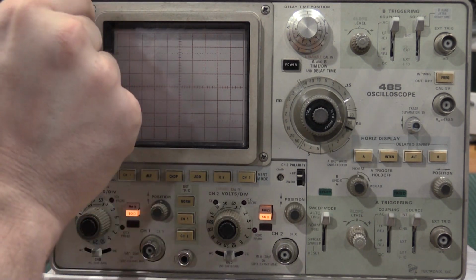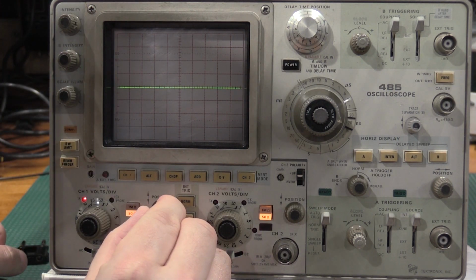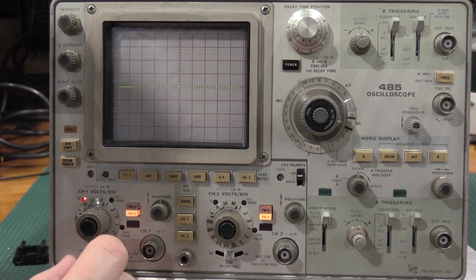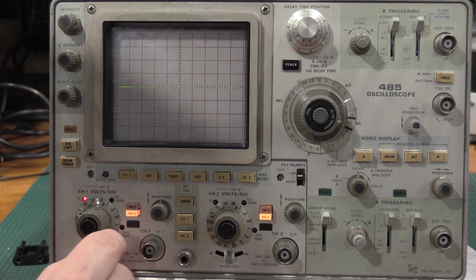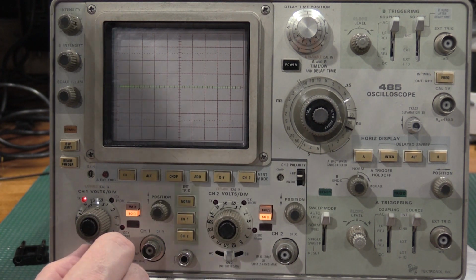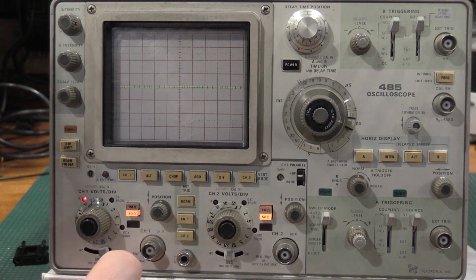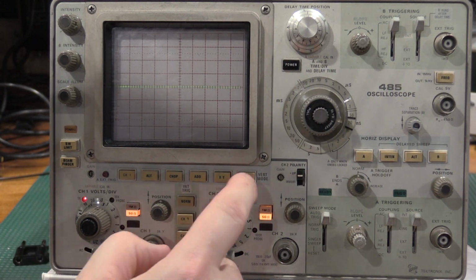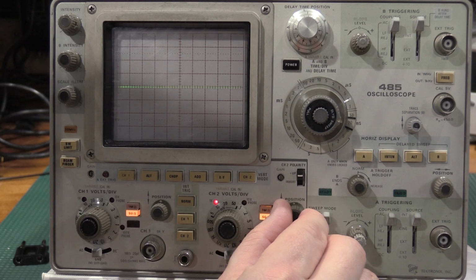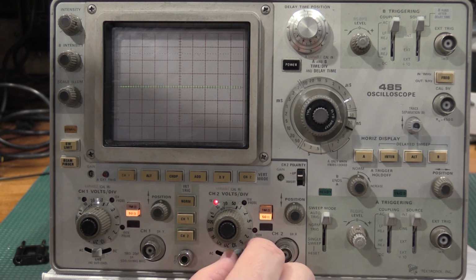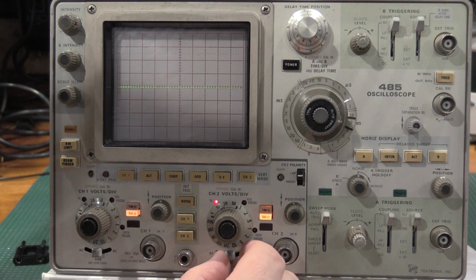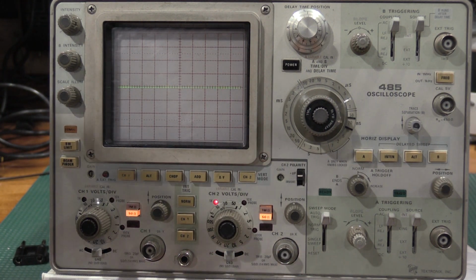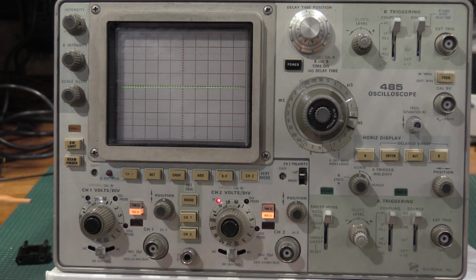Okay, for this we're checking input current, so let's turn this on. Center that. DC and back to ground on the 10 millivolts scale. And the trace should not move up and down. If it does move up and down, you need to adjust 206 and 306. For no trace shift, I have no trace shift on channel 1. Channel 2, very minimal trace shift, so that's fine. It's moving just slightly. We'll adjust that real quick, see if we can't make that a little better.